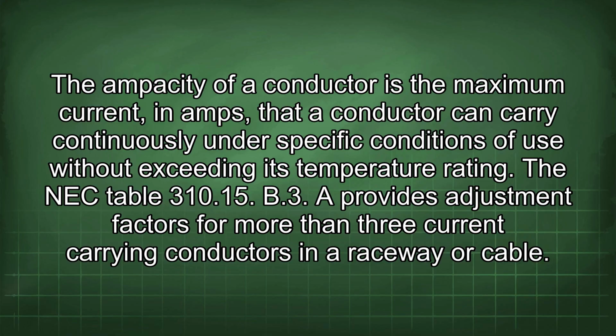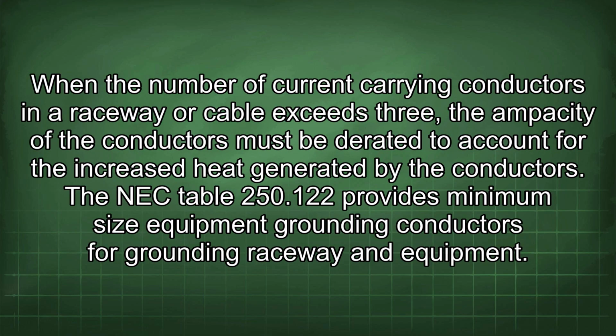The NEC Table 310.15(B)(3) provides adjustment factors for more than 3 current-carrying conductors in a raceway or cable. When the number of current-carrying conductors in a raceway or cable exceeds 3, the ampacity of the conductors must be derated to account for the increased heat generated by the conductors.